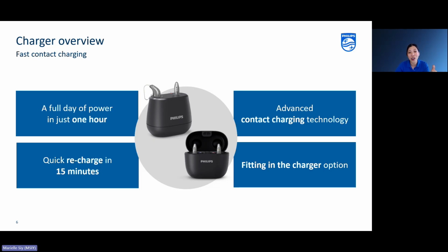So when it comes to the contact charging mechanism, how does it work? When the hearing aids are placed in the charger, the contact points come in contact with the gold springs found inside the charging port. This scraping motion serves two purposes. First, it creates an electrical connection, so it charges. And the second is that it removes any dirt or debris from the contact points. So it's kind of like self-cleaning.